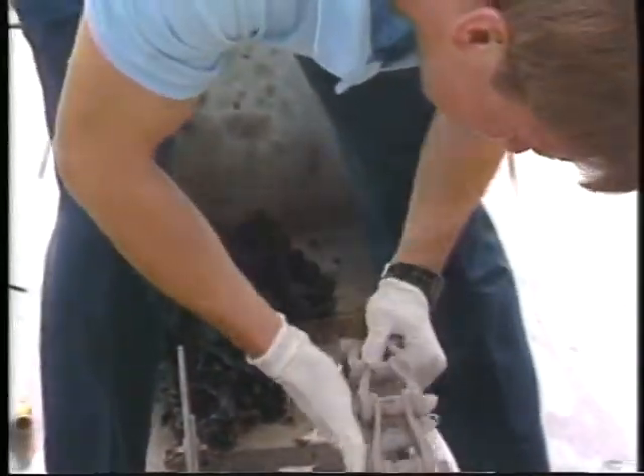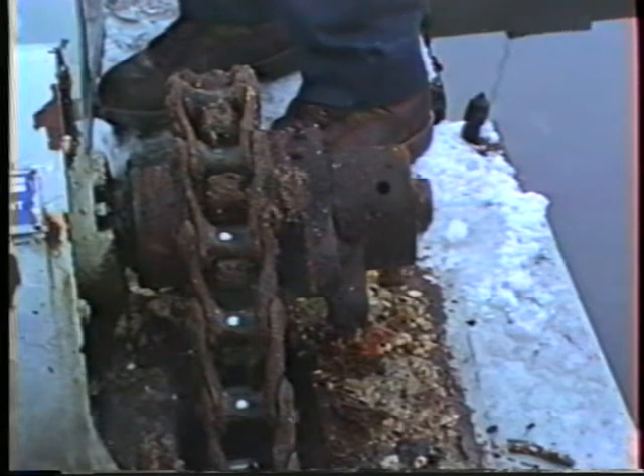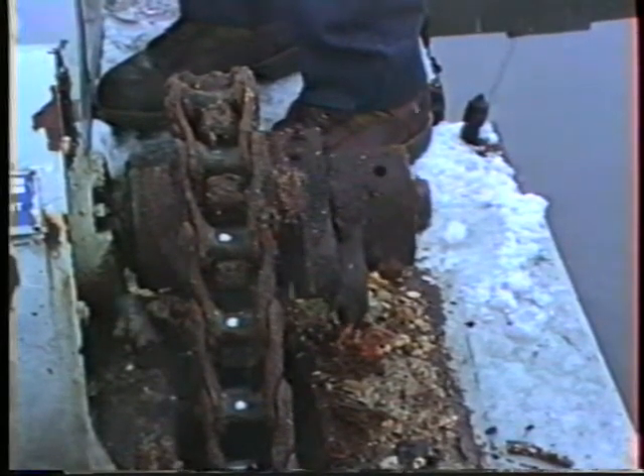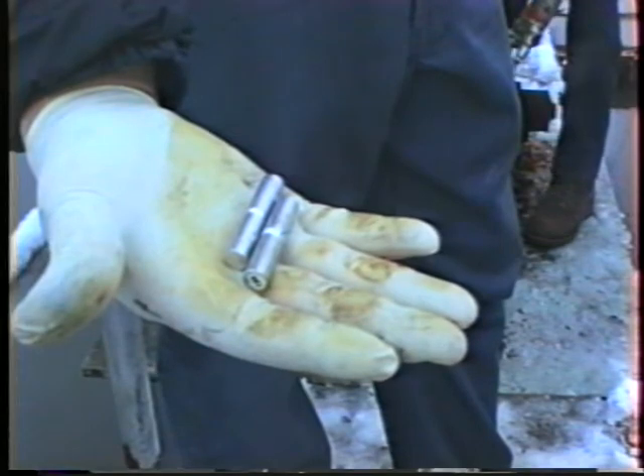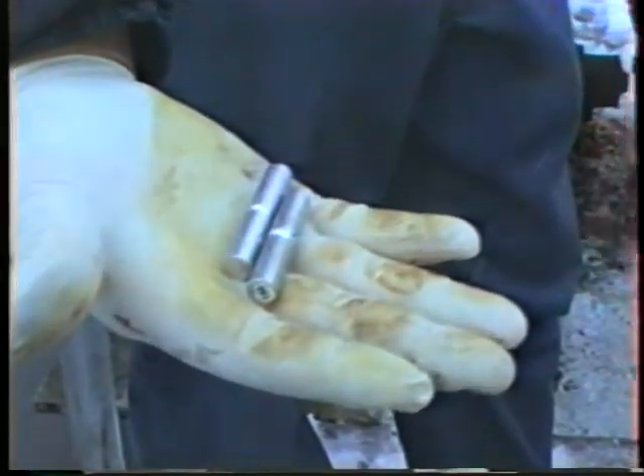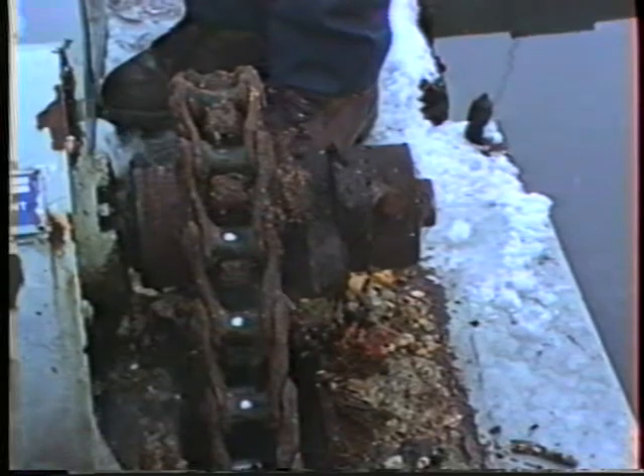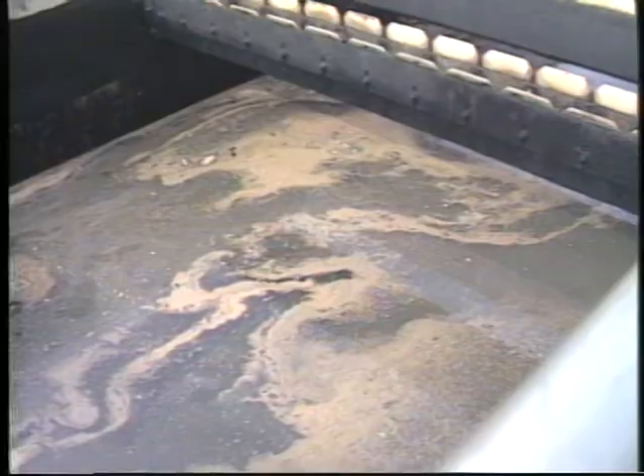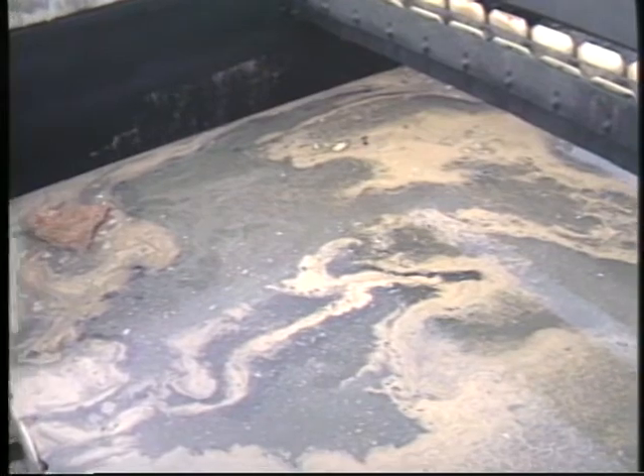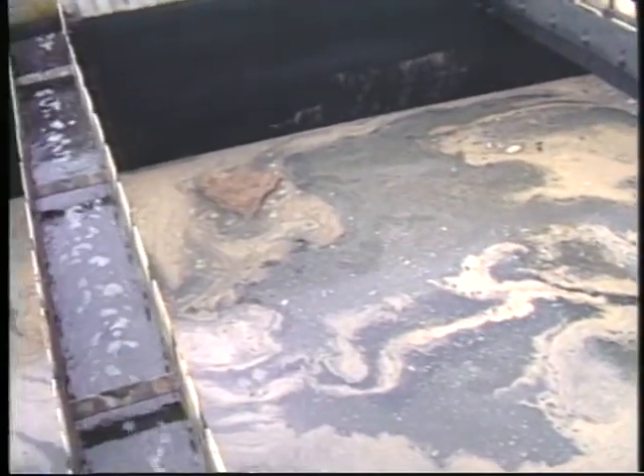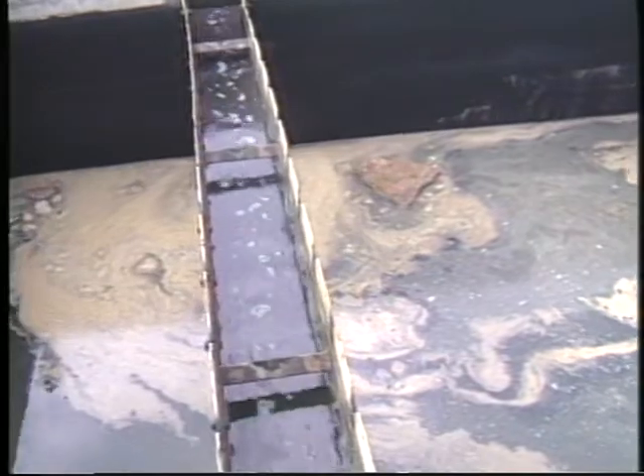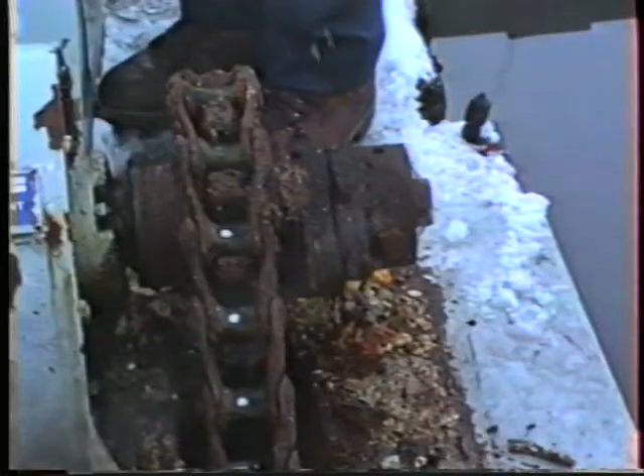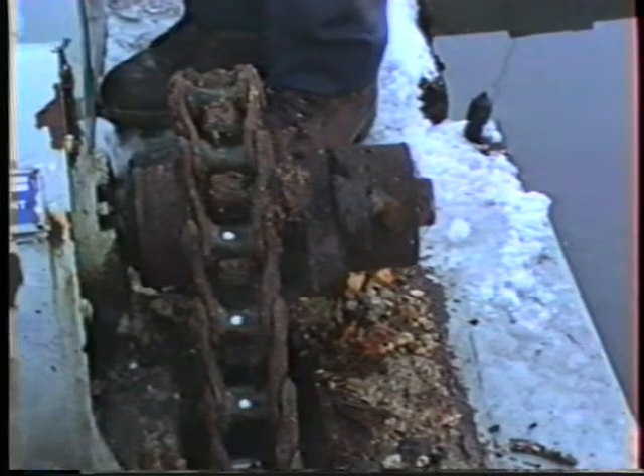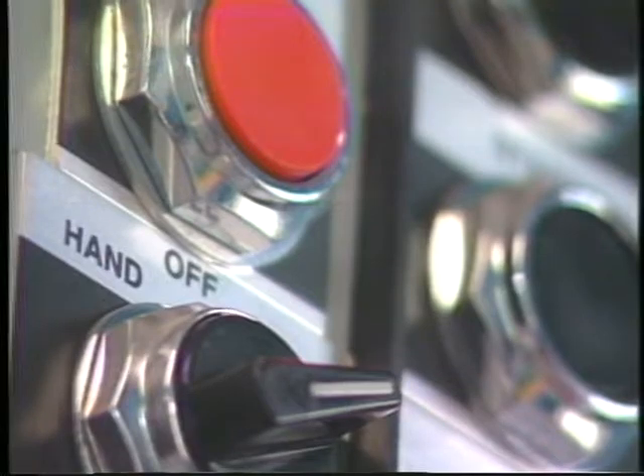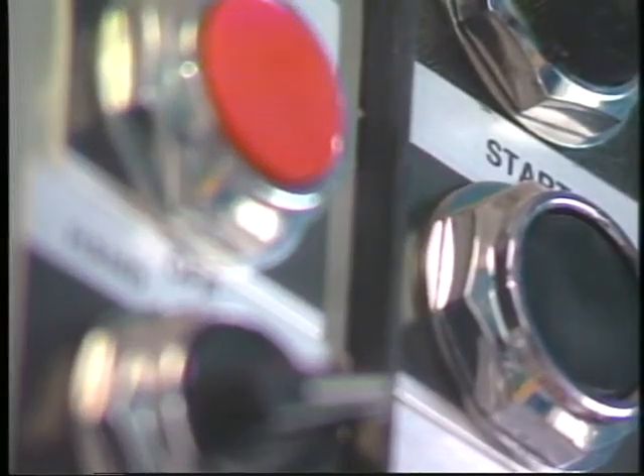If the motor and gearbox are turning and the drive sprocket is not, the problem most likely is a broken shear pin. Shear pins tend to break more frequently in winter months when ice on the clarifier surface interferes with proper operation. An excess of solids in the clarifier, the presence of debris, or a mechanism jam can cause a shear pin to break as well. In any event, the cause of the shear pin failure should be determined before restarting the mechanism. Restarting the mechanism with a heavier shear pin is not the answer and could cause serious damage to the collection mechanism.